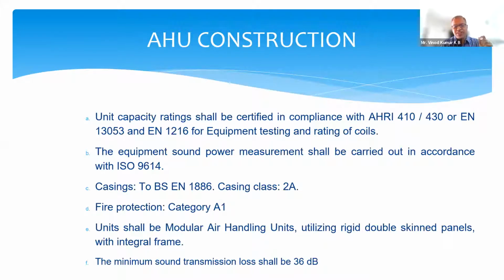Secondly, coming back to the casing, why it is important to follow this standard is because many of the air handlers you will be looking at will have a lot of condensation on top of them, water droplets on the outside of the air handlers. If this air handler is installed inside the ceiling above your head, there will be water dripping onto your head or on the floor. So the casing is important, not only for the strength of the air handlers, but also to see that the thickness of the casing is appropriate in line with the standards.